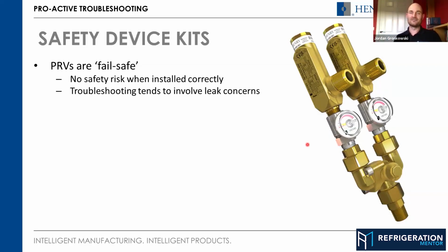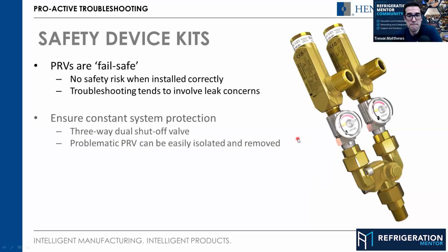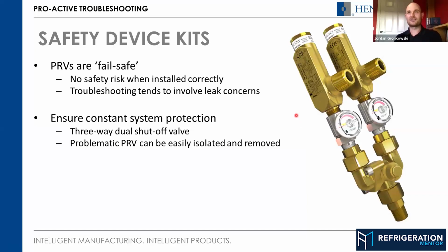So from a system pressure point of view, there's not really a safety risk for a PRV failing. So when you're troubleshooting PRVs, it tends to be because you've got a leak, or because there's a defect in the valve that's causing it to leak out. As I say, unless there's something really wrong with the valve, it should not open, if that makes sense. So there are two ways that you can be proactive in ensuring you're ready to troubleshoot something like this. The first one here is the three-way dual shutoff valve. So this is the device at the bottom here.